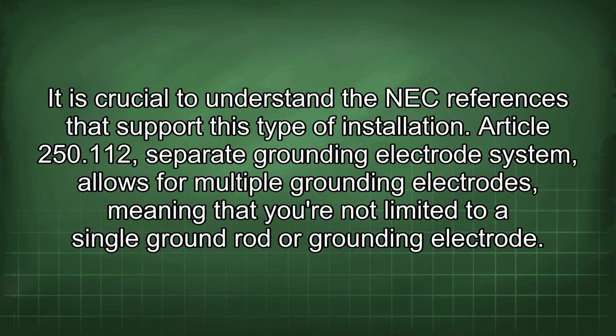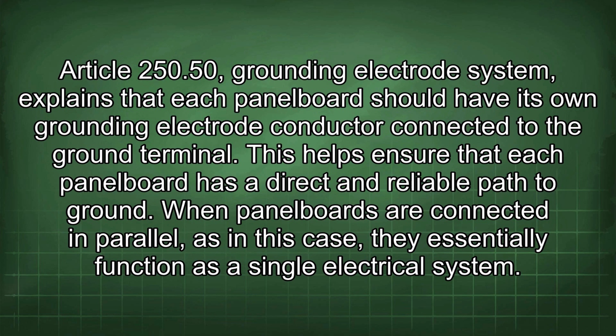Article 250.112, separate grounding electrode system, allows for multiple grounding electrodes, meaning that you're not limited to a single ground rod or grounding electrode. Article 250.50, grounding electrode system, explains that each panel board should have its own grounding electrode conductor connected to the ground terminal. This helps ensure that each panel board has a direct and reliable path to ground.